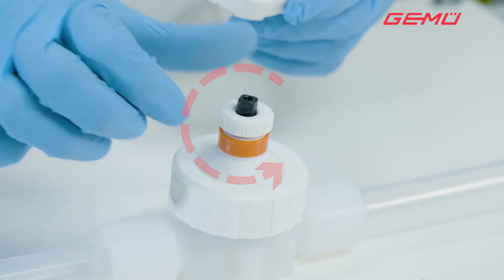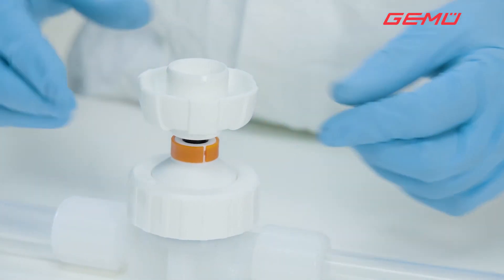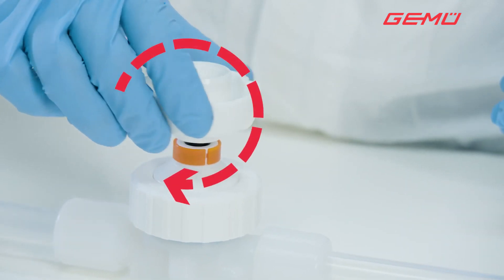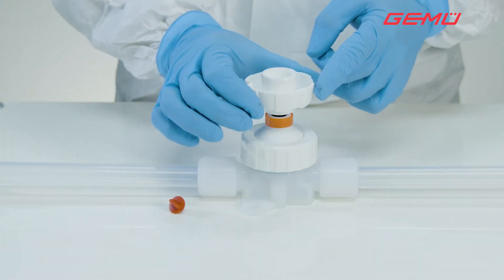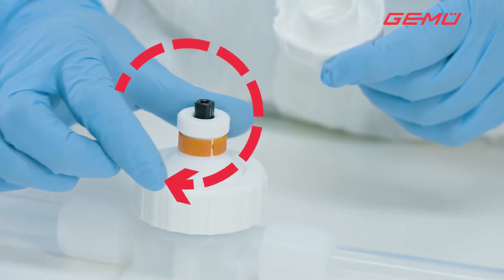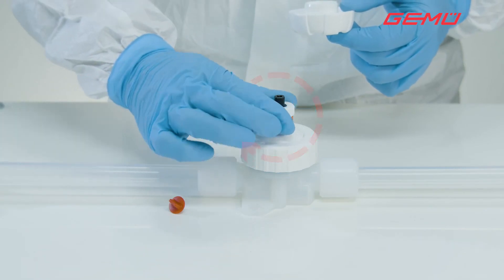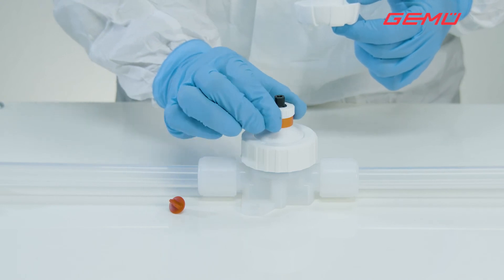Position the handwheel the other way around on the threaded spindle and close the valve by turning clockwise until considerable resistance can be felt. Then remove the handwheel again and tighten the knurled screw clockwise and downwards as far as it will go.